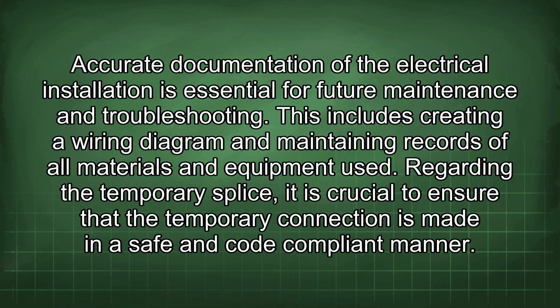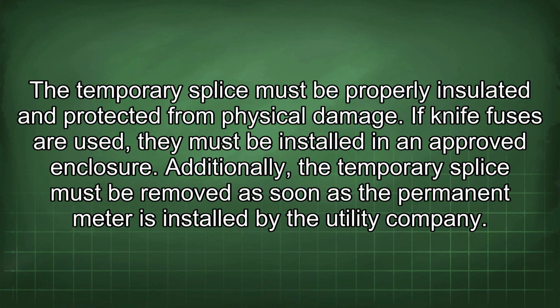Regarding the temporary splice, it is crucial to ensure that the temporary connection is made in a safe and code-compliant manner. The temporary splice must be properly insulated and protected from physical damage. If knife fuses are used, they must be installed in an approved enclosure. Additionally, the temporary splice must be removed as soon as the permanent meter is installed by the utility company.